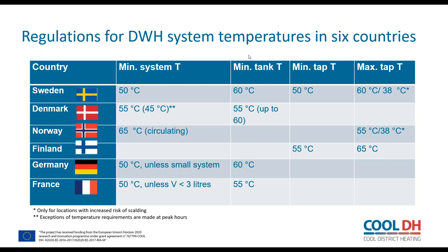Okay, this slide Steen already showed you. It shows the different temperature requirements for different systems for the different countries that we looked into. In general, all countries have regulation on domestic hot water temperature within the range or above the range of Legionella growth. However, the minimum system temperature differs between the countries. Norway and Finland have the highest temperature levels, and Denmark, Germany, and France have the lowest. As Steen also said, in Denmark we have 45 degrees during peak hours, and Germany and France apply the 3-liter rule, which allows lower temperature if the volume of the domestic hot water system is less than 3 liters.